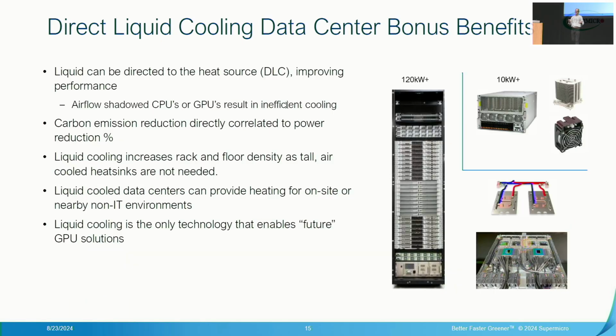What are some of the bonus effects of direct liquid cooling? I have a picture of a 10 kilowatt GPU server with air-cooled heat sinks that are fairly large. With direct liquid cooling, that cooling plate is much thinner, so you get a lot of compression, meaning you can put more in a rack and save floor space at the data center level.